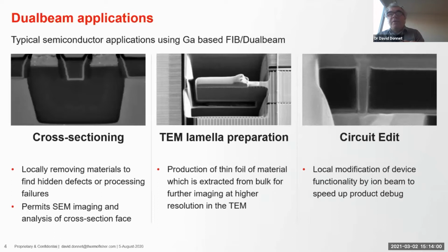To take that one step further, when we need truly high-resolution information and we need elemental information, then we do TEM lamella prep. And TEM lamella prep is maybe the most popular application on the dual beam. There's upwards of, I think, 500,000 lamella made in Thermo Fisher systems per year across the world. So this is something customers are doing 24/7, and nowadays they're doing this completely automated.